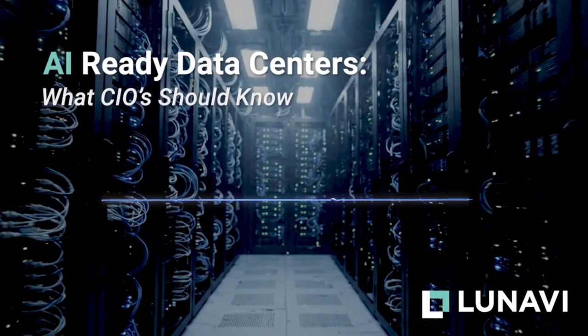But even a closed loop can leak. And a leak inside a server rack is the ultimate CIO nightmare. Oh, it's the absolute worst case scenario, which is why mitigation becomes the primary focus of facility management. Right. CIOs must architect continuous leak detection systems across every inch of the manifold. We are talking about sensors that can detect a pressure drop of a fraction of a PSI. Wow, that's sensitive. Yeah, and they're tied to automated shutoff valves that can instantly isolate a single failing rack without disrupting the fluid flow to the rest of the data center.